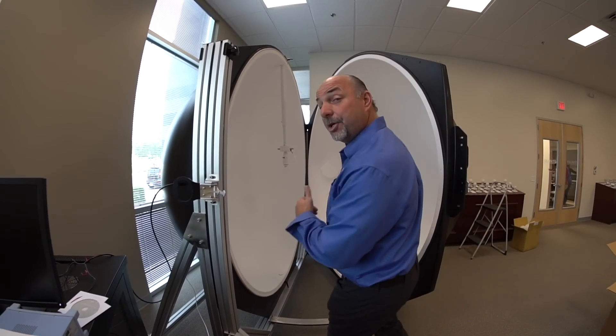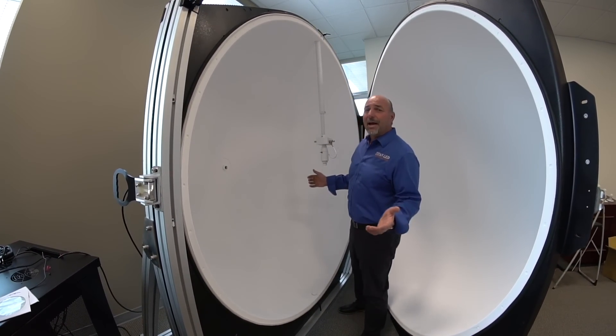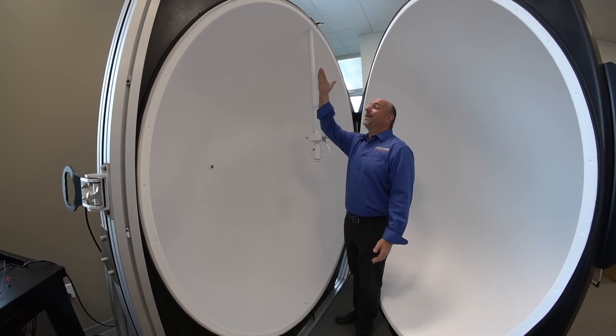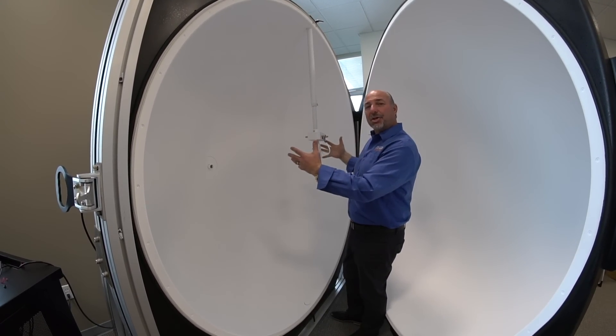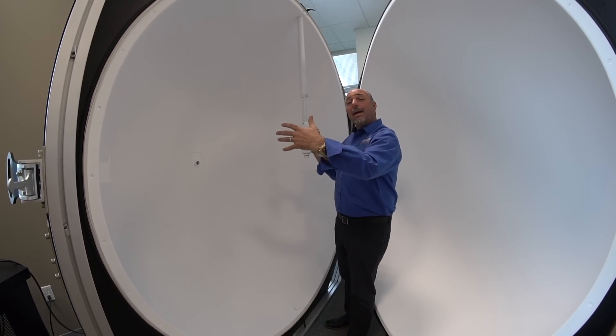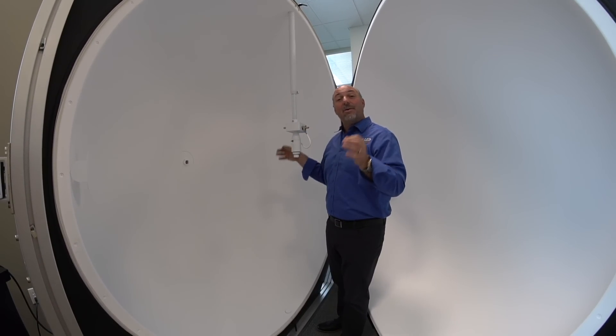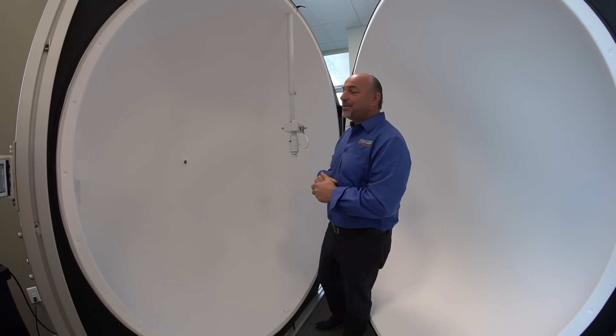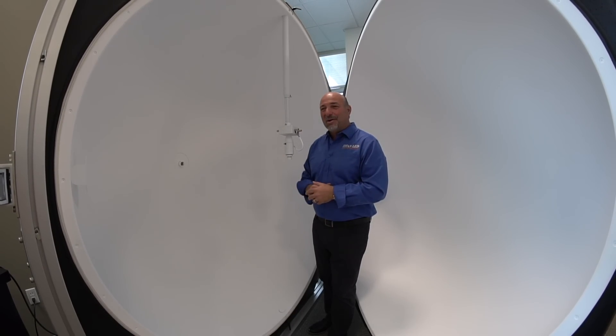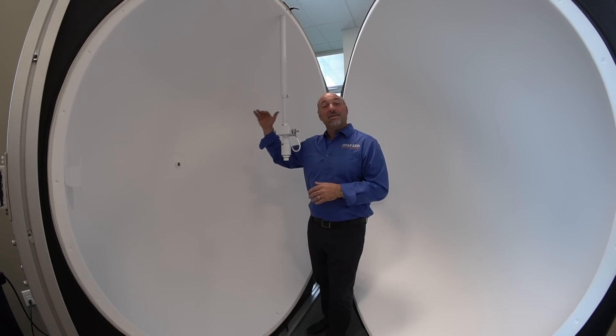It's a 2-meter sphere, and the reason we had to get a 2-meter is that the top of our business is 4-foot tubes. If you've got less than a 2-meter sphere, you can't test a 4-foot tube. This is the actual hanging device for the sphere — the luminaire will actually go in here. Whether we're testing a 4-foot tube, a 2-foot tube, a high bay, a shoe box, or a wall pack, this sphere can test up to 100,000 lumens. None of our units have gotten to 100,000 lumens yet; we're up to about 67,000.